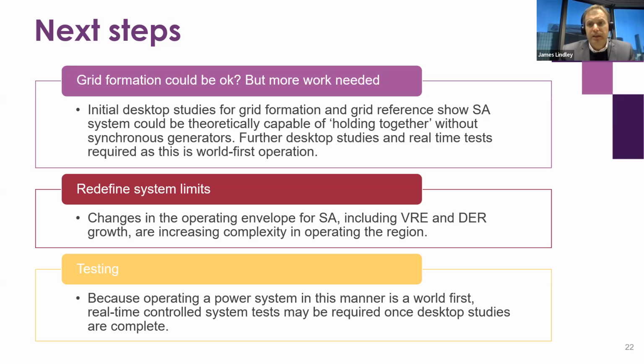Probably the biggest and most challenging part of that work was grid formation - can we run the power system with synchronous condensers and inverter-based generation alone, noting that almost all of that inverter-based generation is grid following, not grid forming. The only real grid forming battery we have in the system is quite small and energy limited.